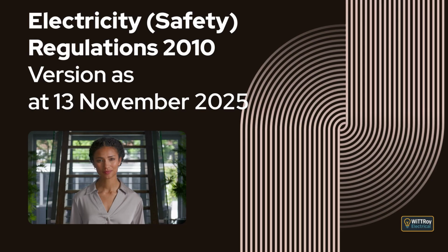It also explains that a used appliance is considered electrically safe at the time of sale if it has been tested, inspected, and tagged in accordance with AS/NZS 3760, or has been disabled and marked in accordance with AS/NZS 4701, or, for used electrical medical devices, has been tested and marked in accordance with AS/NZS 3551. The regulation finishes by explaining that selling or supplying a fitting or appliance that is known to be, or is recklessly supplied as, electrically unsafe is an offence and carries a Level 2 penalty.